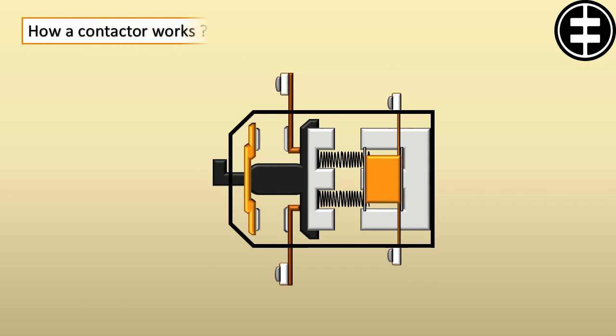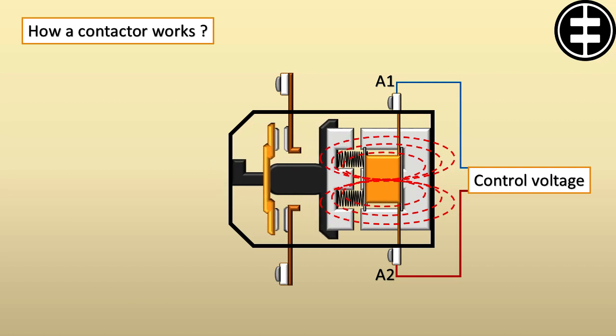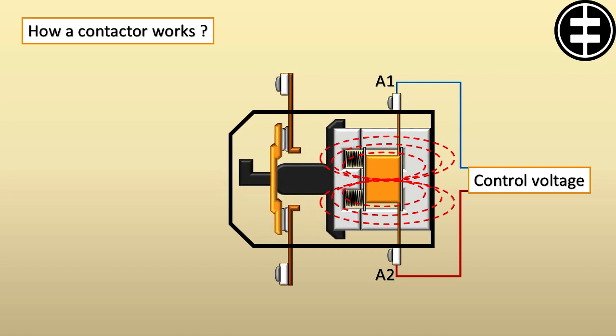How a contactor works: When applying the control voltage on the coil leads A1 and A2, a magnetic field will be generated, attracting the movable iron core towards the fixed core. So the movable contacts which are fixed to the movable core will move as well towards the fixed contacts to make contact and allow the power lines to run to the load.